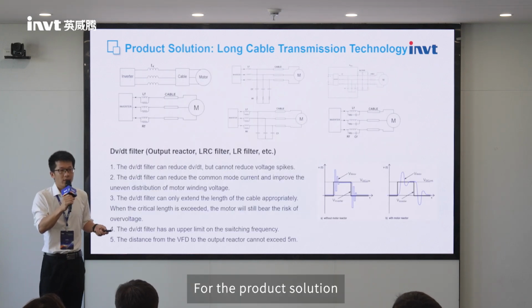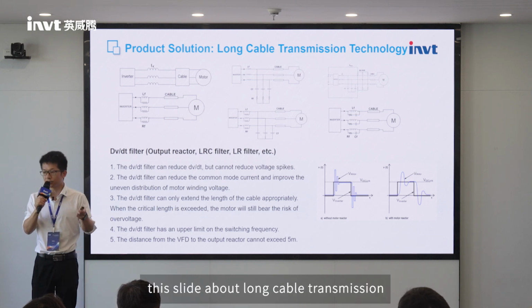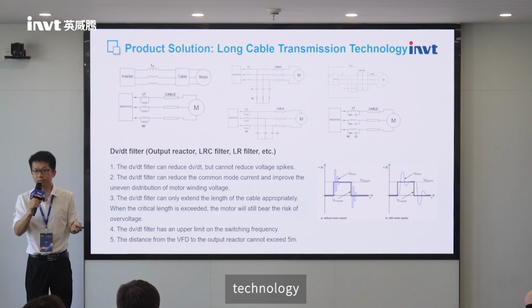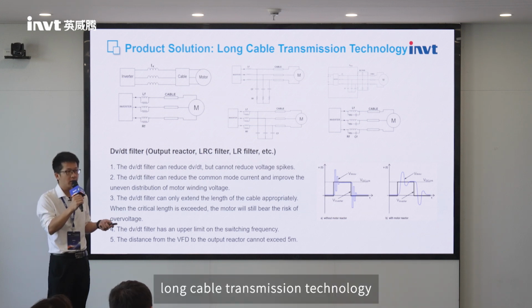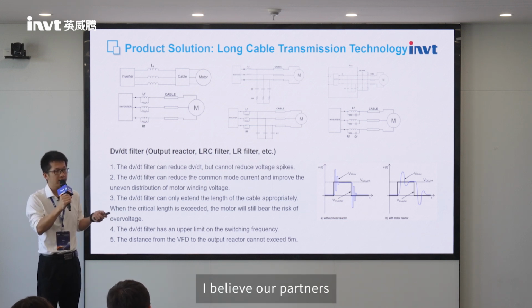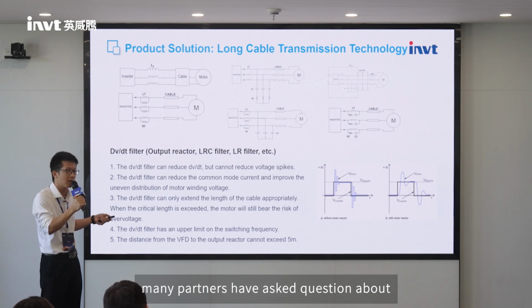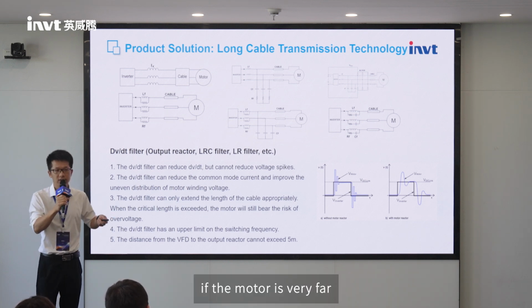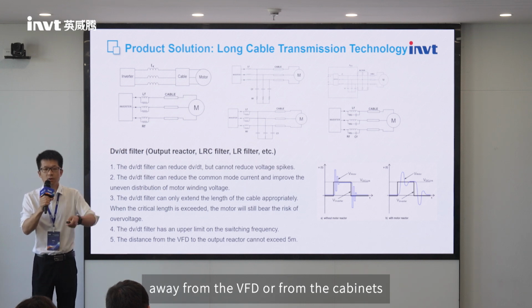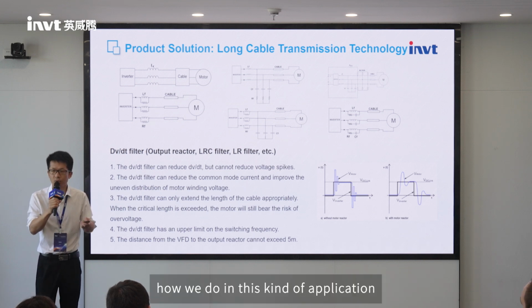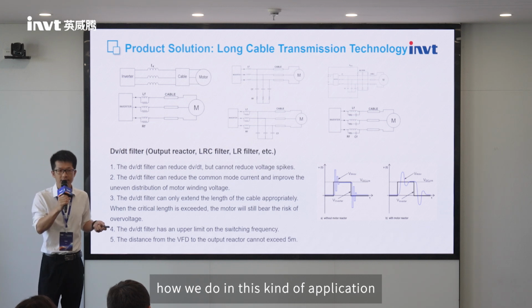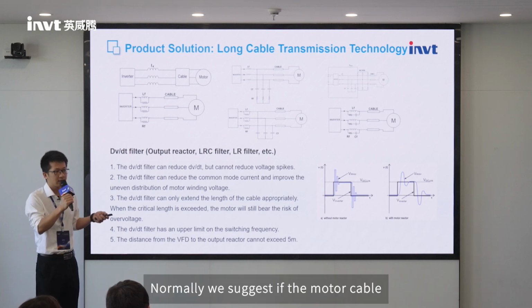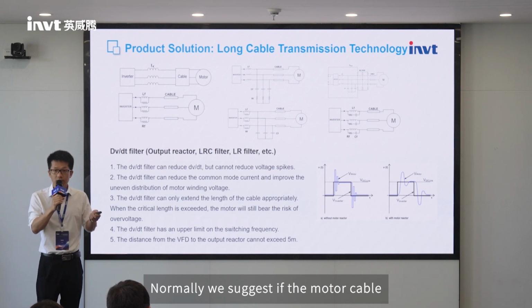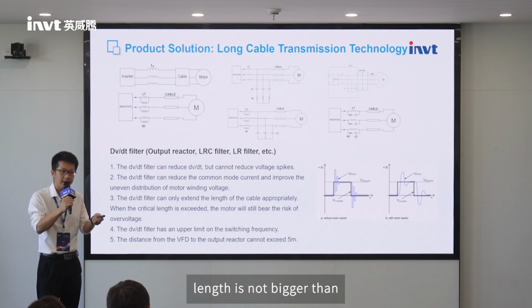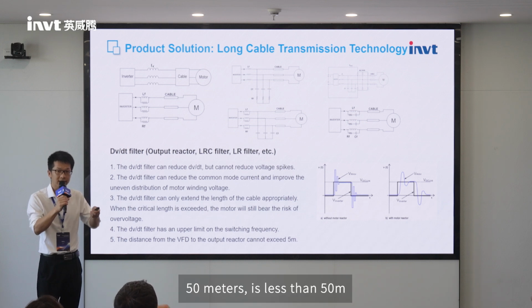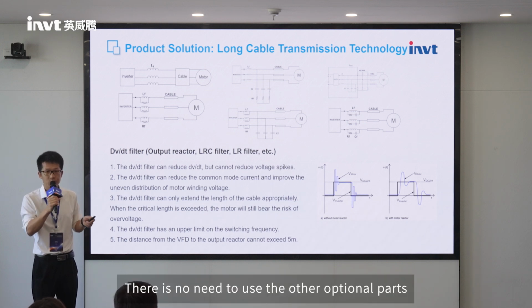Okay, for the product solution, this slide is about long cable transmission technology. I believe many partners have asked this question: if the motor is very far away from the VFD or the cabinet, how do we handle this kind of application? Normally, we suggest if the cable length is less than 50 meters, there's no need to use any optional part.